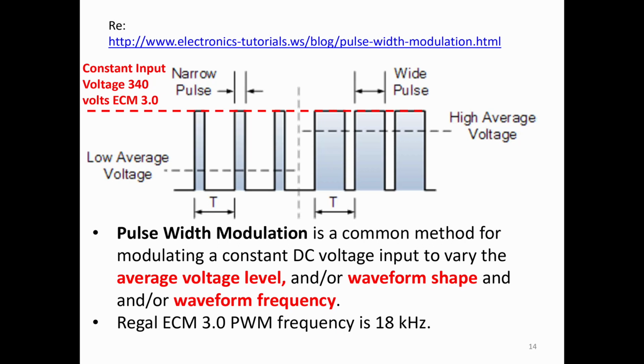And over the right-hand segment, you would get a higher voltage, and over the left-hand segment, you would get a lower average voltage. So lower average voltage, higher average voltage. But in all cases, you have a pulse train frequency of 18 kilohertz. And that's the problem, because if you have a square wave, you have harmonics. If you had a perfect square wave, you would have harmonics at all the odd frequencies. I have no idea what the spectrum looks like for a pulse width modulation unit, but I can tell you from experience that it can produce significant harmonics.